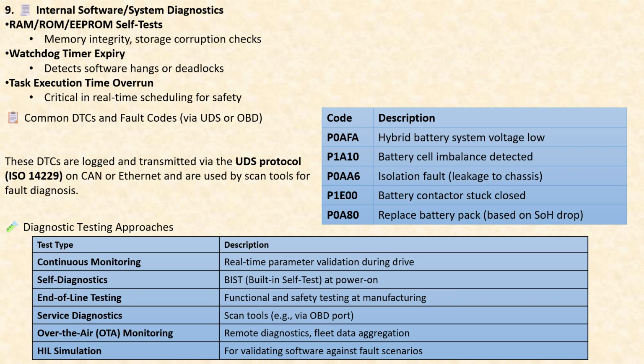Now, when it comes to internal software system diagnostics, the various areas like RAM, ROM, EEPROM self-test, memory integrity and storage corruption checks must be thoroughly checked. Watchdog timer expiry detects software hangs or deadlocks. Task execution time overrun is critical in real-time scheduling for safety. And this is common for DTC and fault codes.